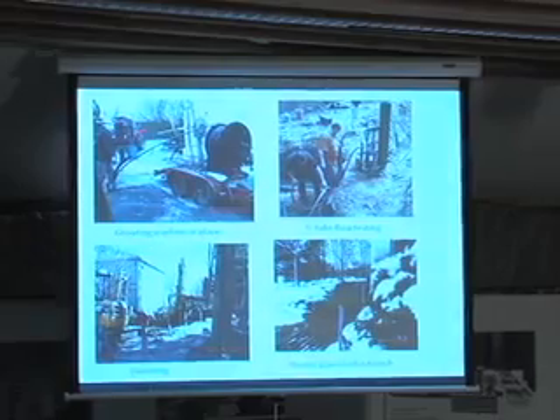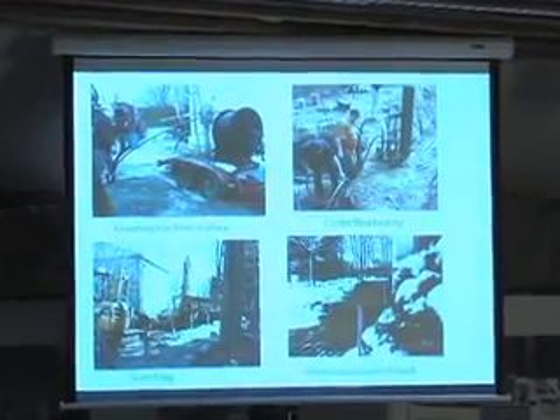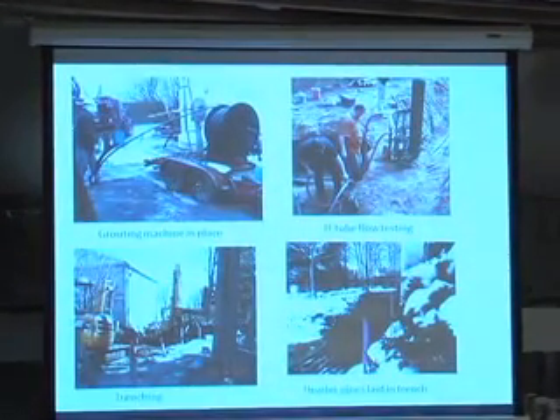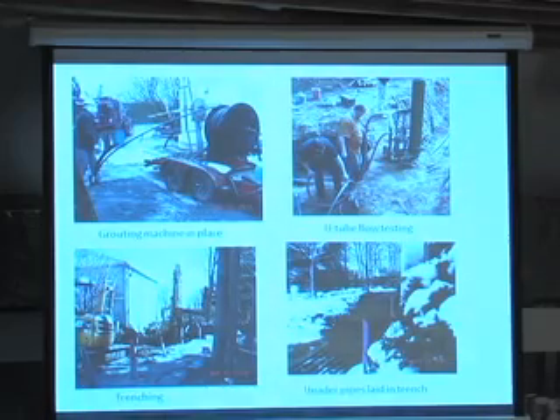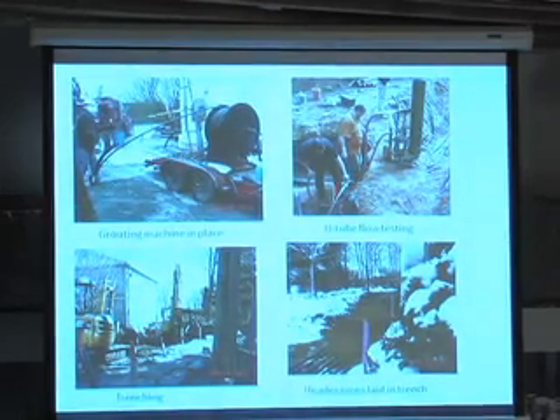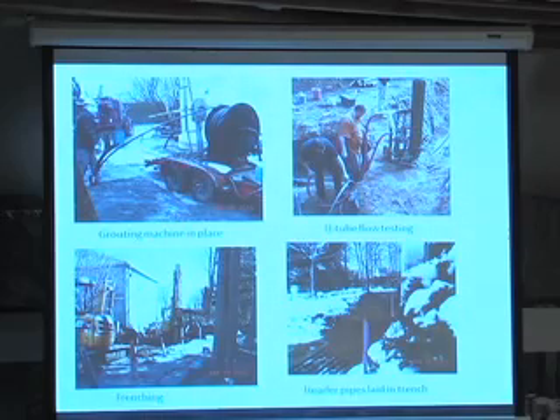Okay. Here's how you do the grouting. Remember the vertical boreholes? You plug in the U-tube. You have to grout it. The reason you grout it is that it's an EPA, DEP requirement. You don't want the surface water to run into the borehole, and the different aquifer layers in the ground to get cross-contaminated. So you grout the whole thing. And here we do the flow testing for the U-tubes once they are grouted and in the ground.